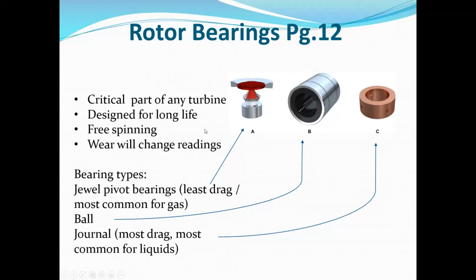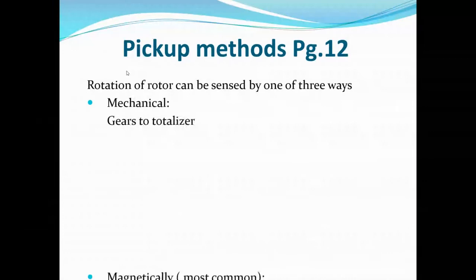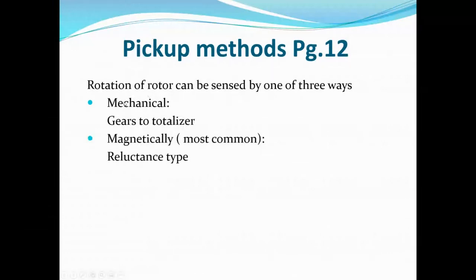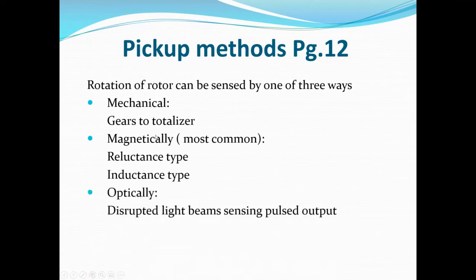The most important parts of a turbine meter are the pickups. Rotation of the rotor can be sensed three ways: first, mechanically — rotors coupled through gears to a mechanical totalizer, still used in some applications. Second, and most common, is a magnetic style pickup — specifically a reluctance type or an inductance type. Third is an optical style pickup, which detects disrupted light beams relative to the pulse output from the turbine meter.